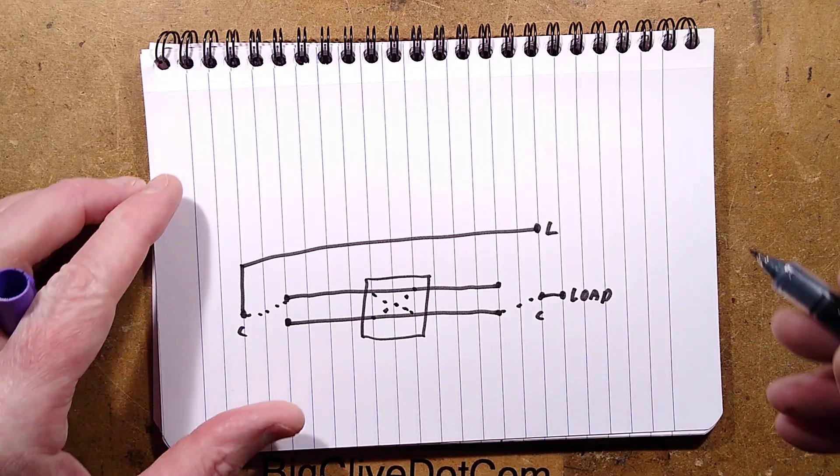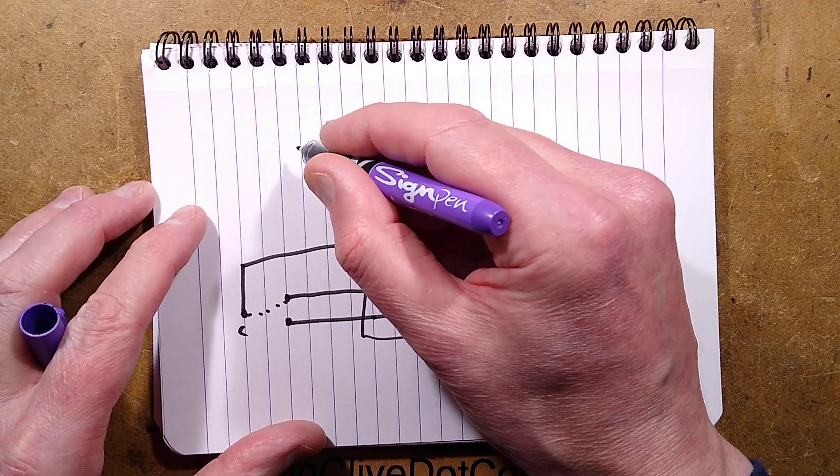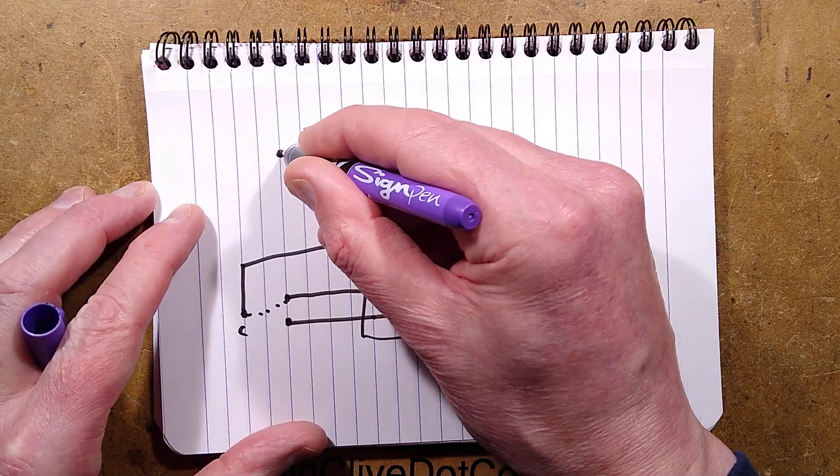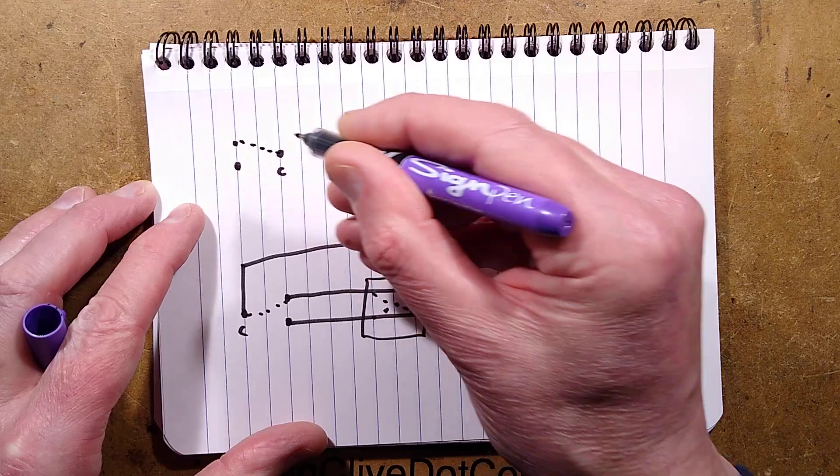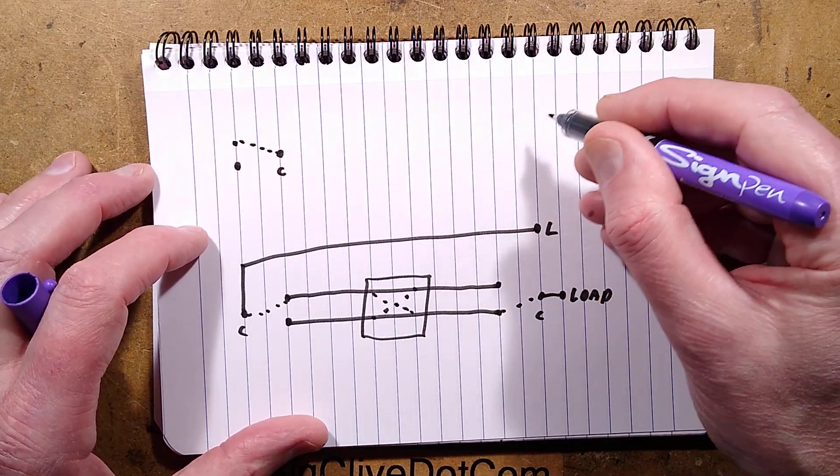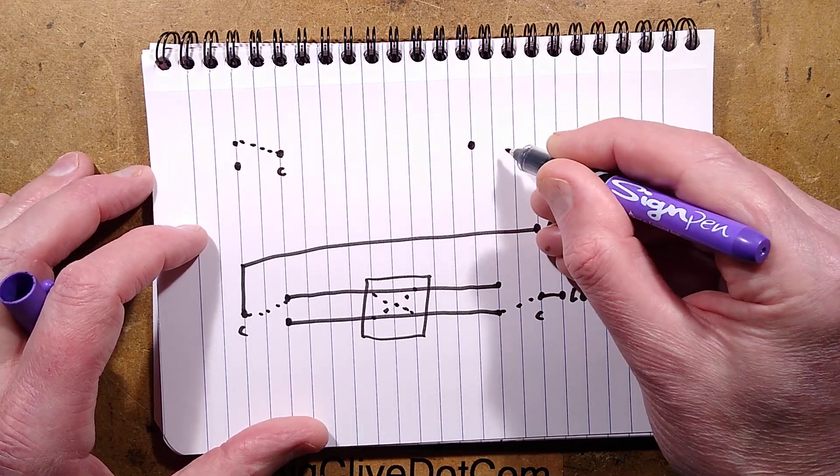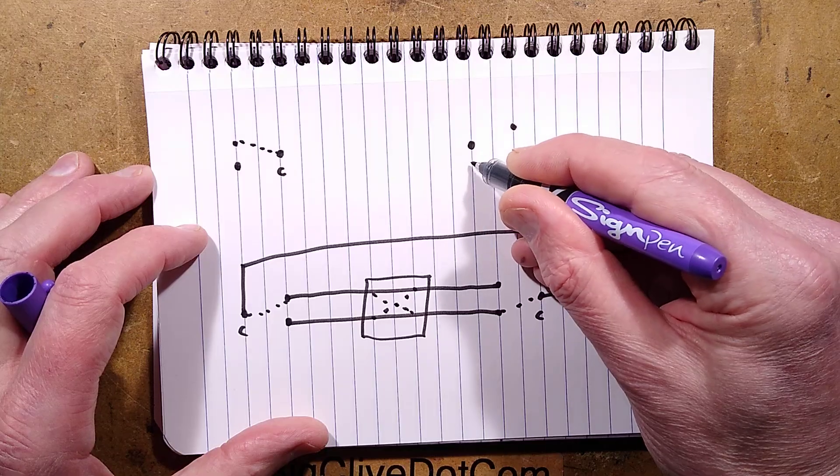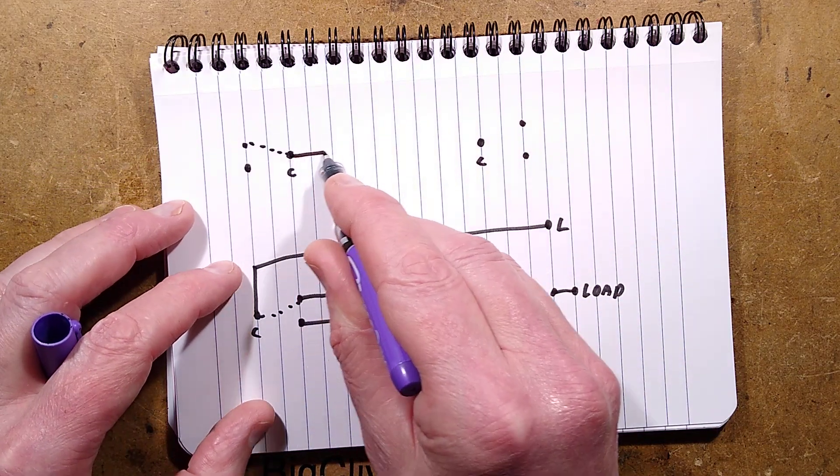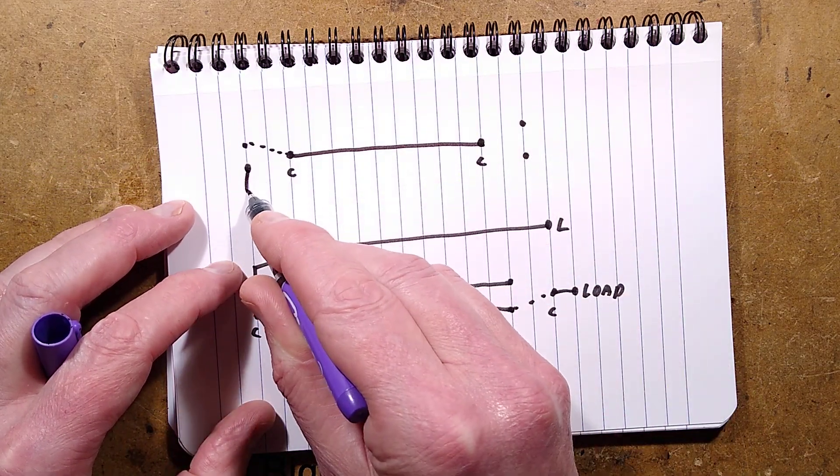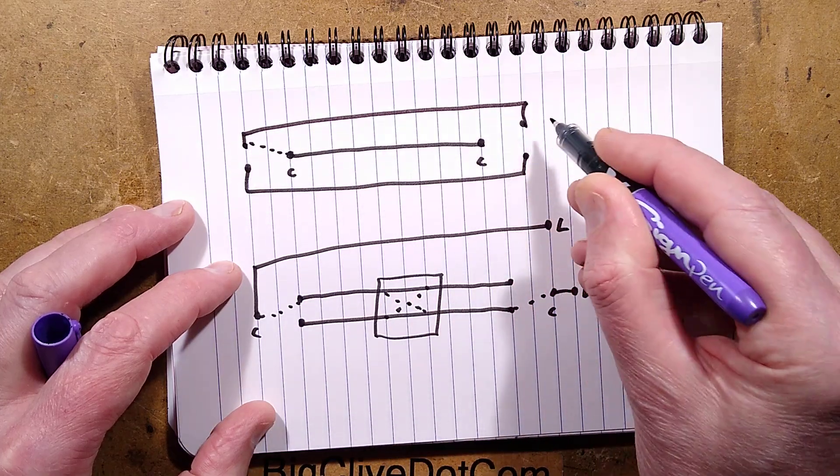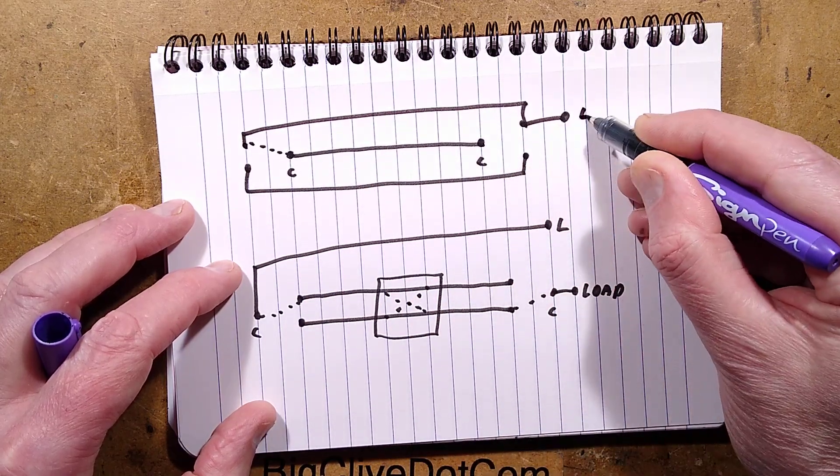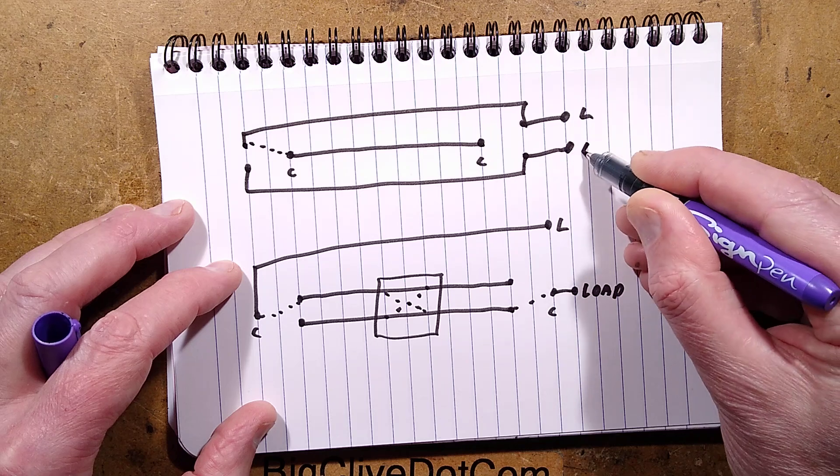Now the other way you can wire them, and it's my preferred way to be honest, is to have your common, the two connections - I'll just show one of them made - and here's the one at the other end and the two connections. There's a common again, and I bridge the common and I bridge the other connections like this, and then you've got live and load.